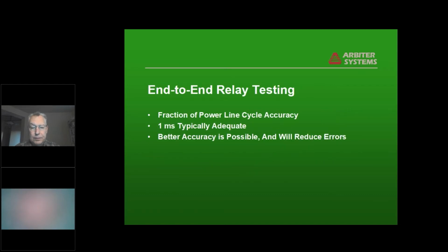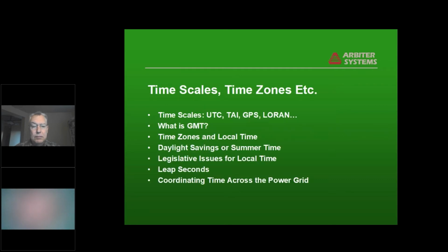And then relay testing. Generally, a millisecond is accurate, or adequate. It's a similar kind of thing to the fault recording scenario. And accuracy typically can be made much better. It can be made easily 1,000 times better as far as the synchronization signal that's available to the relay tester. So again, certainly possible with today's technology.